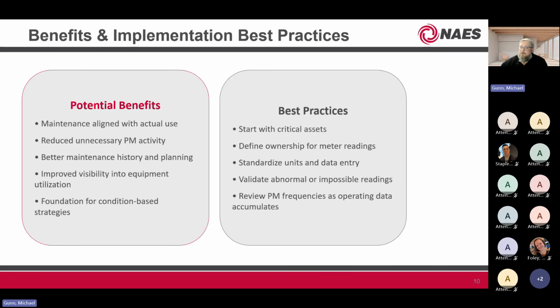If you standardize the way data is entered and the units used, it makes it much easier to analyze later. Also make sure you're validating abnormal readings. Say DP jumps up 200 pounds one day and the next day it's back to normal differential pressure - more often than not that's just someone like myself with large fingers entering information incorrectly, adding an extra zero or something. So you have to keep an eye out for those readings.